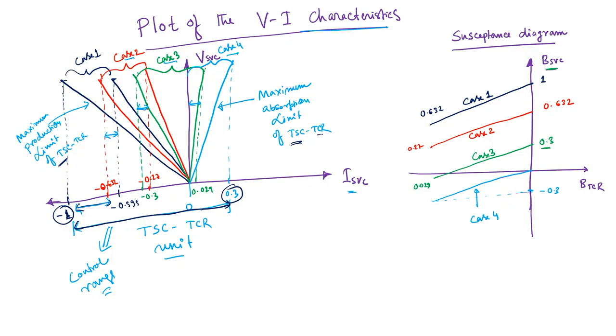And with the variation of TCR, it is possible to have a smooth control of the TCR susceptance in each of the cases, and thereby we are able to produce or absorb VAR within this control range to any value. So this is something one needs to understand.